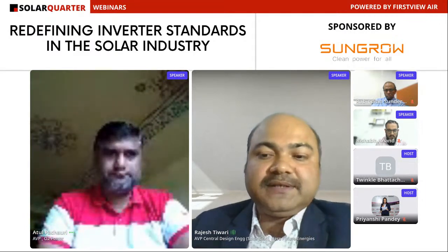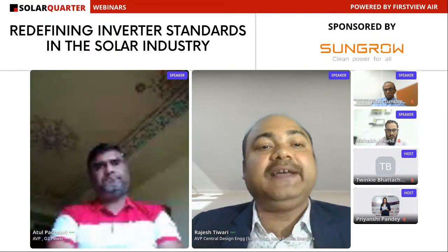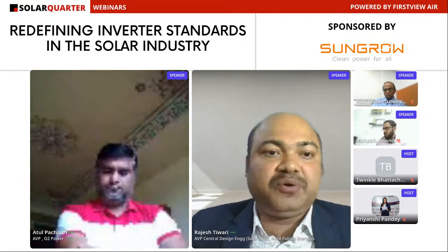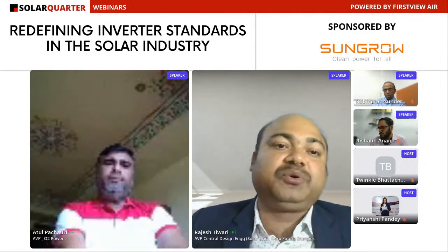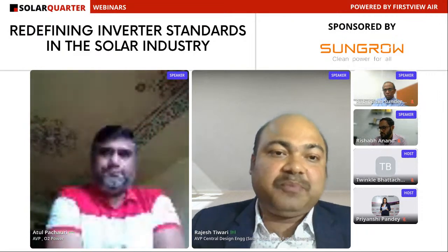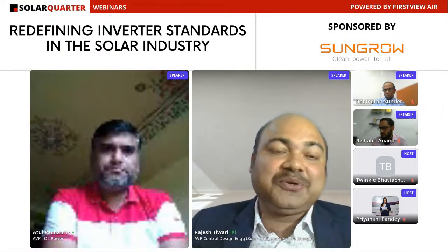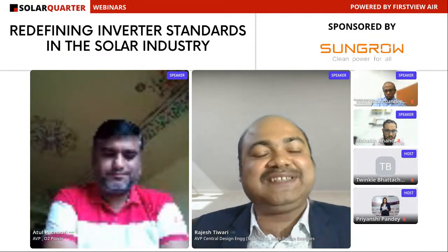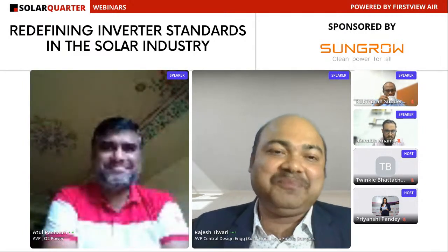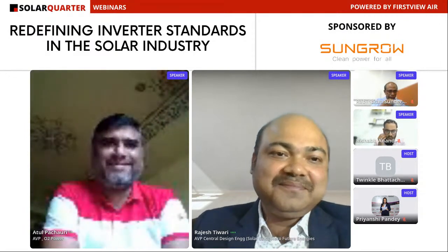On the AC side, there is a kind of LT panel. So if 2000 volt comes, then definitely the ratio may increase, or 800 volt may become 1000 volt AC, so 1.1 kV will also be there. So availability of MCCB or switchgear is also required. So definitely this helps reduce the BOS, but technology challenges will also be there that we have to manage. Absolutely right, sir. So we are taking note of it.